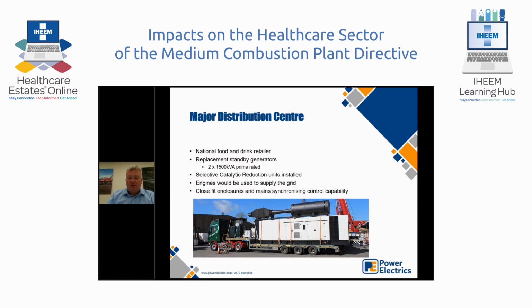But that's on a new installation with containers. We're currently involved with a few projects doing refurbs and retrofits of these units into existing plant rooms. Sometimes they go on the roof of the plant room, sometimes inside. It's basically finding the exact space, while keeping back pressure reduced to a minimum, and getting the SCR as close to the end of the generator as possible to ensure the integrity of it working.